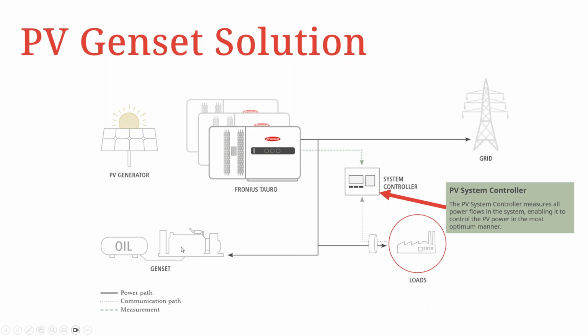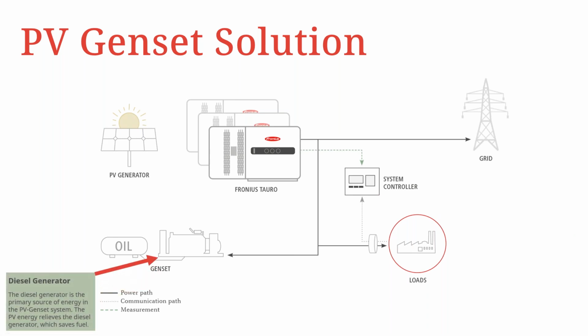The same effect is also handed to the genset, to determine when to ramp down with the complement of the PV injection into the system. The genset, of course, is the primary source of energy in this system. Like I said, we target setups that have gensets that are almost perpetually running. So this genset tends to be the primary source of energy for this system.